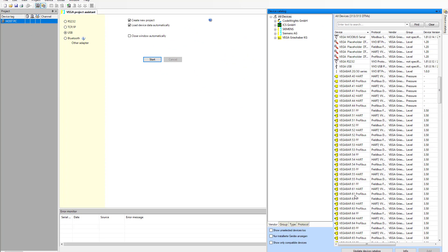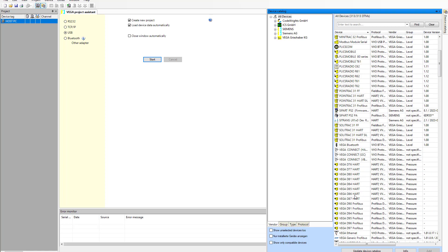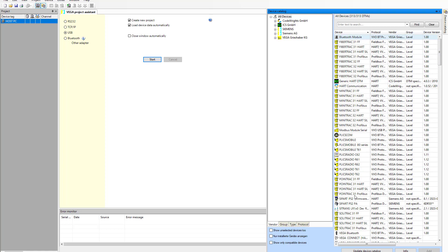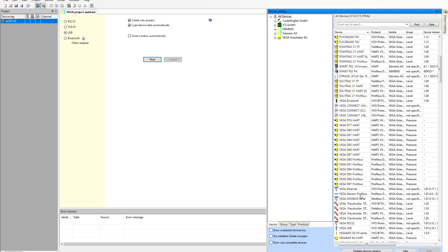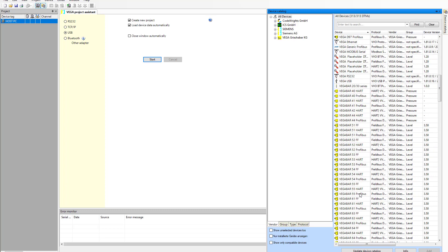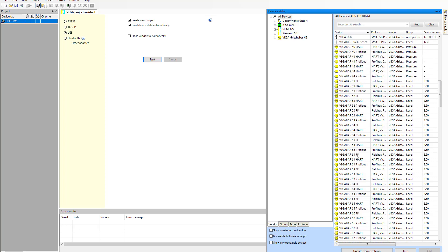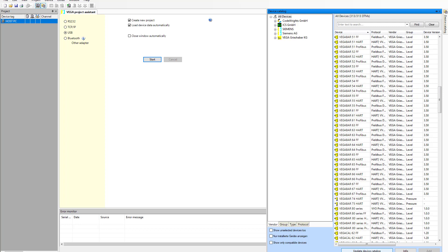Vega was relatively easy to be honest. I just downloaded a catalog with all the Vega stuff in and it pulled it all in. Most manufacturers have a straightforward DTM, so you get like an EXE file that you click on and it installs the device into your catalog, and then you have to update the catalog to bring it into your projects.